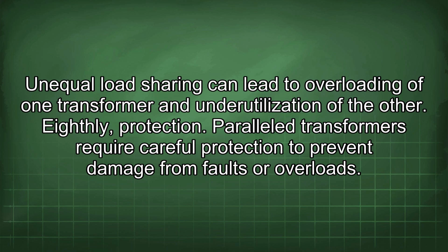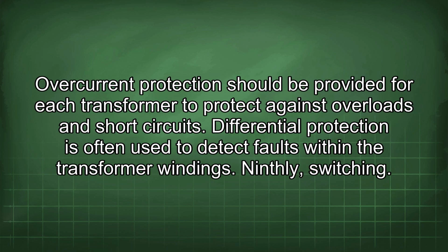Eighthly, protection. Parallel transformers require careful protection to prevent damage from faults or overloads. Overcurrent protection should be provided for each transformer to protect against overloads and short circuits. Differential protection is often used to detect faults within the transformer windings.